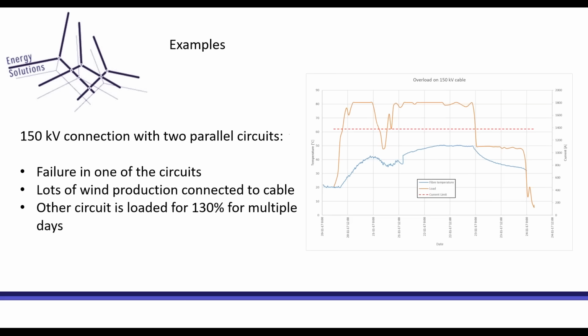connection cable. So the first example was there was a fault in a 150 kV cable connection in one of the circuits. This was indirectly connected to a lot of offshore wind, and in the picture on the right you can see the continuous current limit in red. And the orange one is the load that actually happens during the overload. And the blue line represents the measured temperature of the fiber. This was on the most critical part in the cable connection.